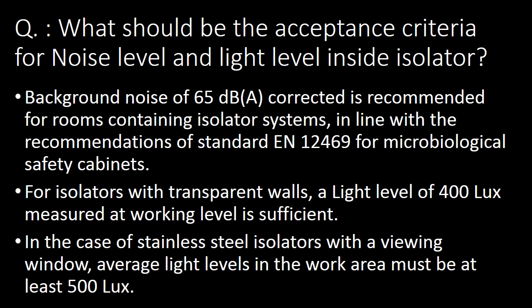The next question: what should be the acceptance criteria for noise level and light level inside the isolator? A background noise of 65 dB(A) corrected is recommended for rooms containing isolator systems. This limit is in line with the recommendations of standard EN 12469 for microbiological safety cabinets.